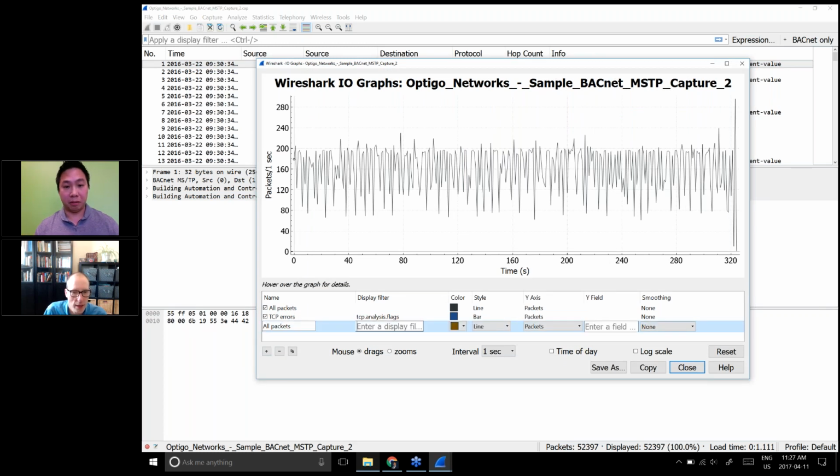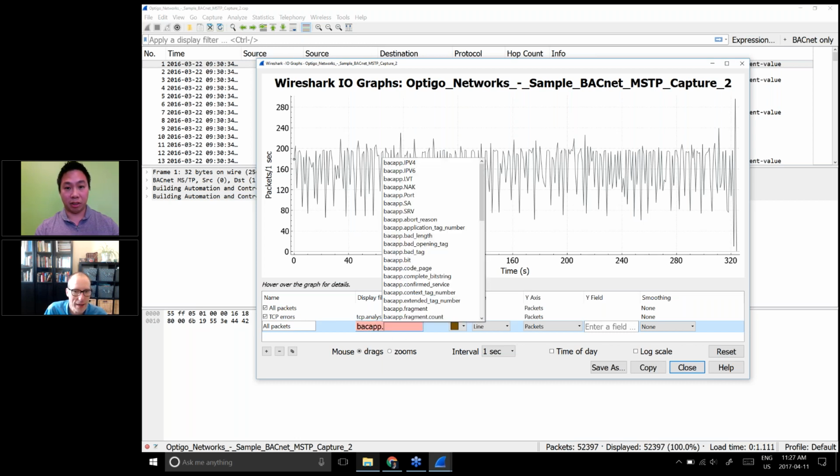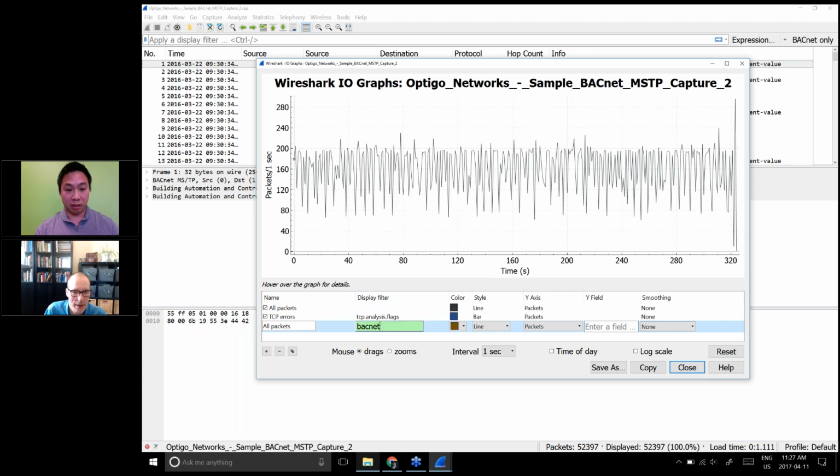So then you could do the global broadcast, that's what I was going to do. It's bacnet.dnet. If you want to do a global broadcast, it's BACnet and then dnet, destination network equals 65535. Okay, 16-bit number. Yep. And then click out of there and make it a bar or something.